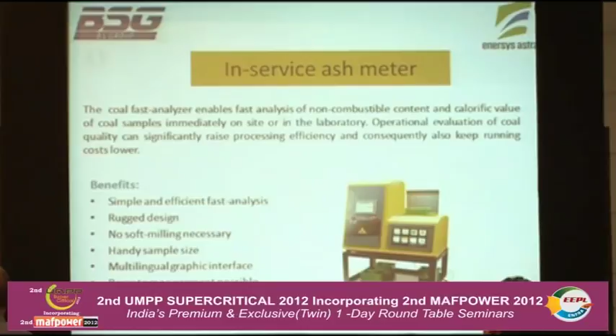Coming to the in-service ash meter, this gives the answer for your GCV analysis, the 48 hours you are talking about. The general scenario today is that when the coal is received at power plants, definitely the stock is not sufficient to do the analysis and then burn it. The moment the coal comes into the stockyard, it is immediately sent on the conveyor belt to the burner. By the time the analysis report comes, there will definitely be a variation in the energy output and the quantity used. That's where we suggest this in-service ash meter, which can be used on-site or even in the laboratory.